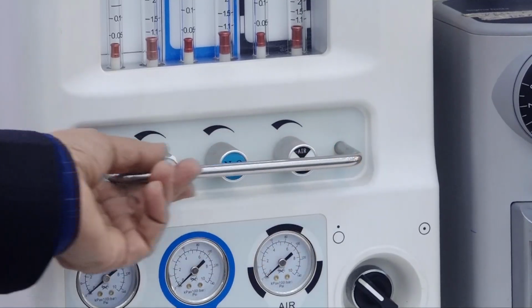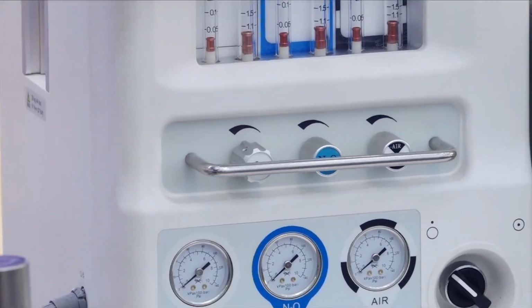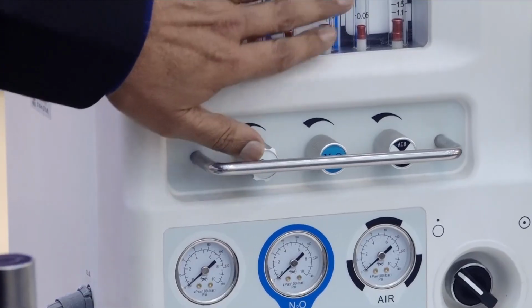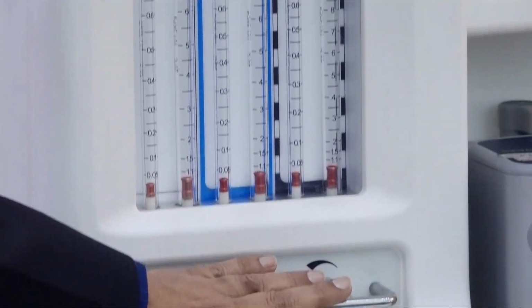Everything is important. They will ask you these things. And coming to the flow meter assembly, between the flow meter assembly and the flow control knobs, you have the proportionating devices, which is called as a Link 25. In case of GE machines, even in this Penlon, you have Link 25. They are mechanical proportionating devices. 95% mechanical, 5% pneumatic.